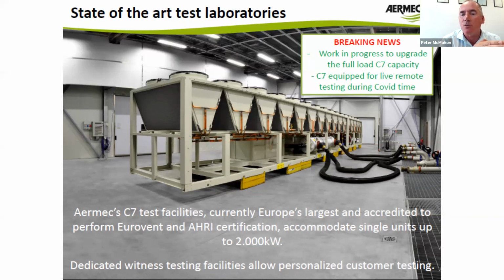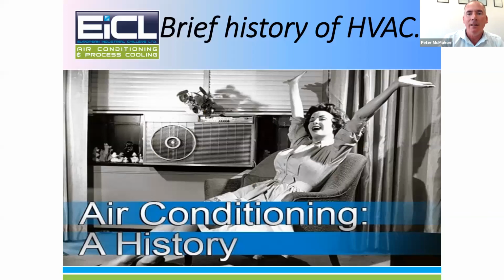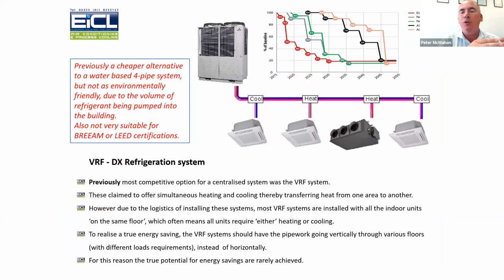So Aermec, one of the manufacturers we represent, have the biggest test chamber in the whole of Europe. And every single chiller heat pump that comes out of that factory is Eurovent certified and tested, which means it's independently verified and tested. So before we get into the multifunctional heat pump, historically, if you wanted simultaneous heating and cooling through a refrigeration system, you would have had a VRF system. These are very common on air conditioning applications. They're relatively cheap and cheerful, I'll say.